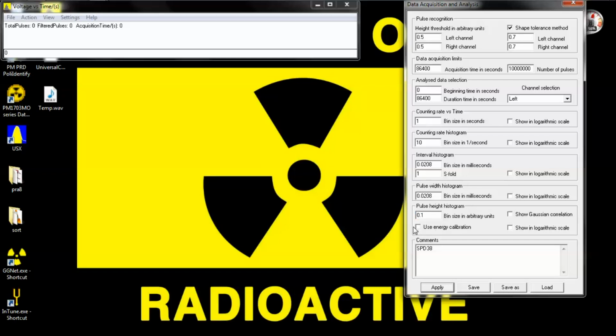Use energy calibration checkbox should be unchecked to start with because you haven't calibrated yet. Once you calibrate the unit, then you'll want to check this box to fix that. And I'll show you what these other units do in just a minute. I'm just giving you the most basic thing you'll need to start with.